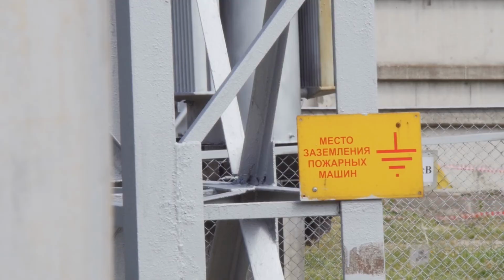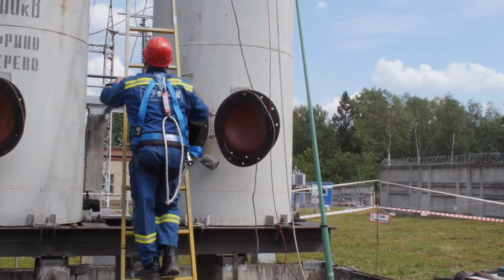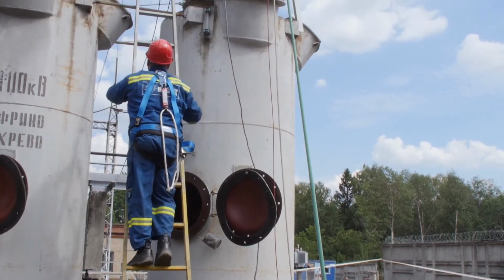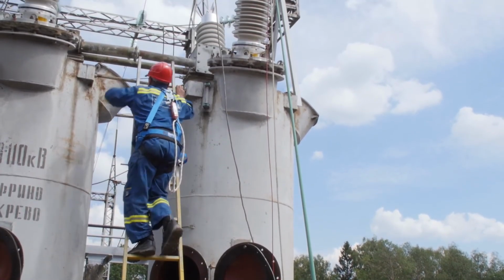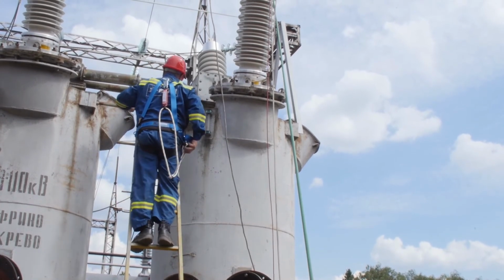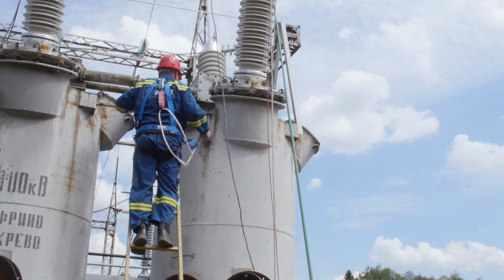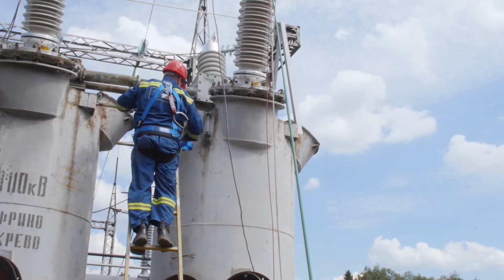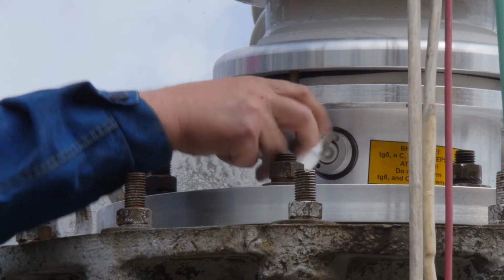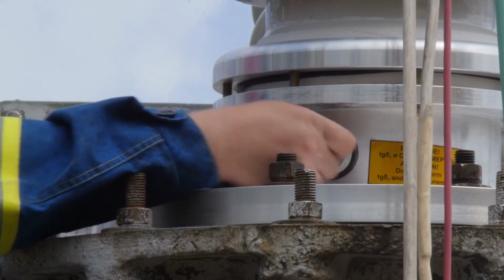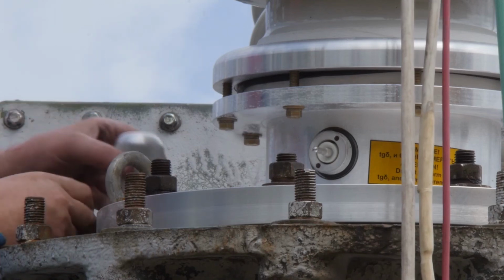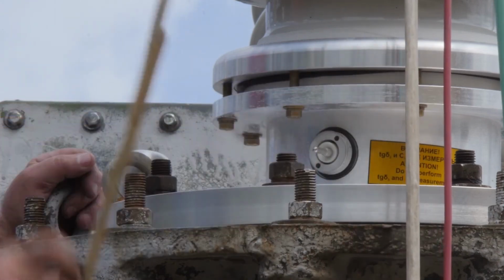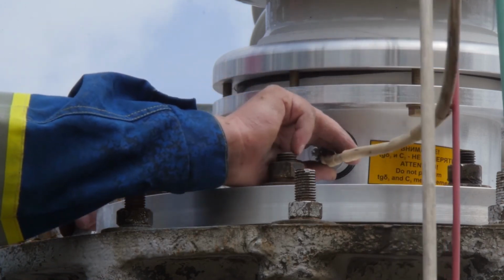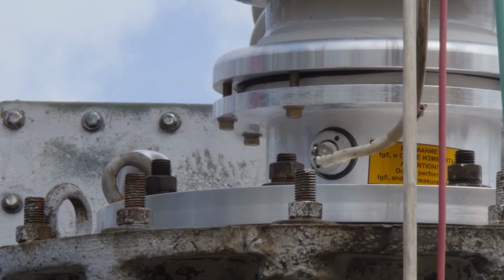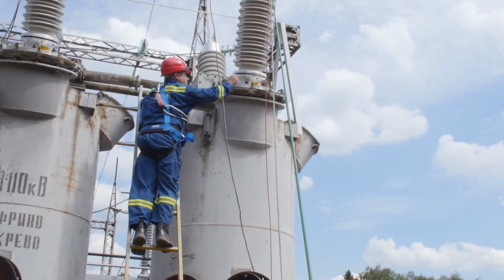Upon completion of operations, the electrical laboratory experts shall make sure all the bushings are provided with grounding elements and the test tap hoods are tightened until compression of the rubber seal. Based on values of parameters to be measured, a conclusion is made with respect to bushing operability. Later on, these values will serve as a reference for the definition of an actual condition of the bushing. In case testing results are positive, a relevant entry is made in the bushing certificate with an indication of installation completion date and signature of a person in charge of installation, and a technical report is drawn up.